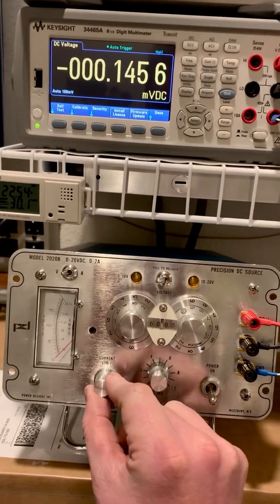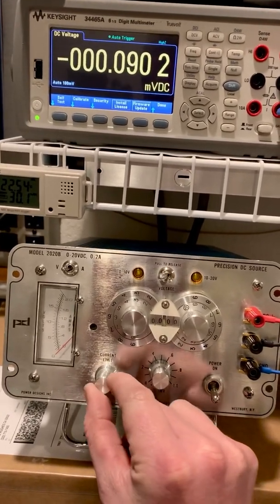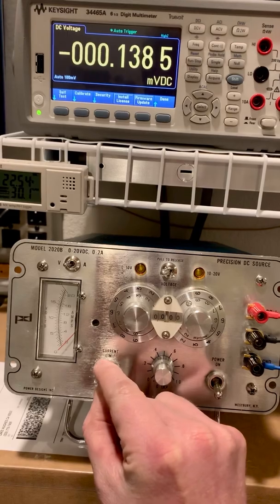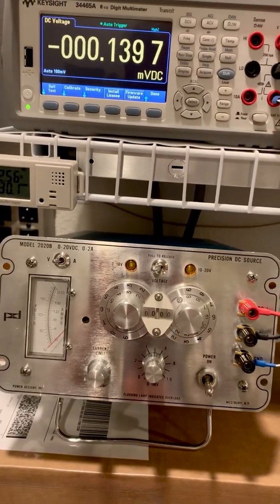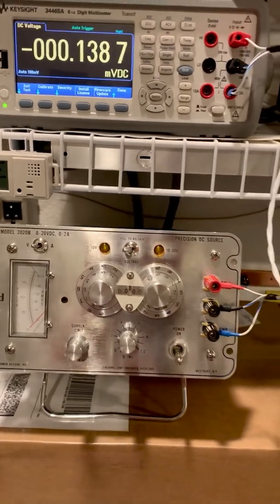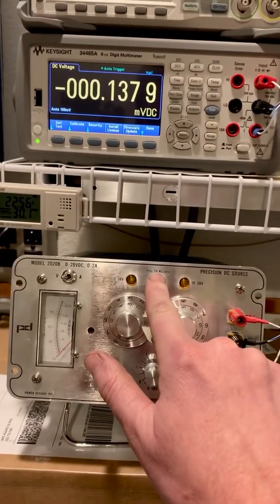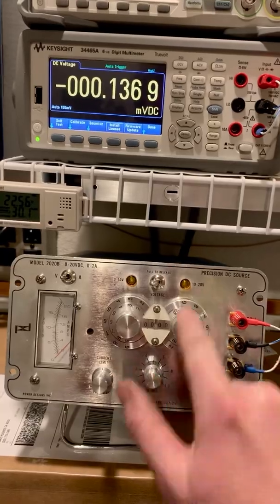Current limit, pulled out to set, adjustable from 0 milliamps up to 0.2 amps. We have a switch here for a 0 to 10 volt range, and then 10 to 20 volt range.